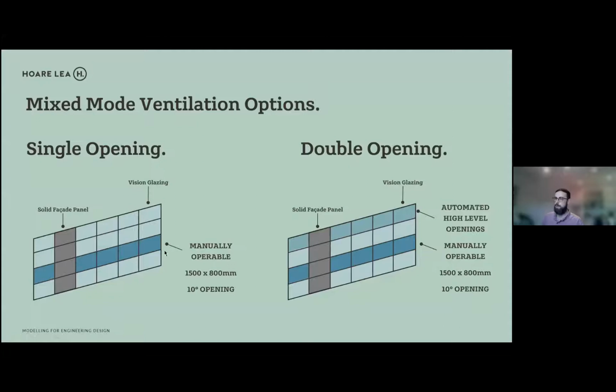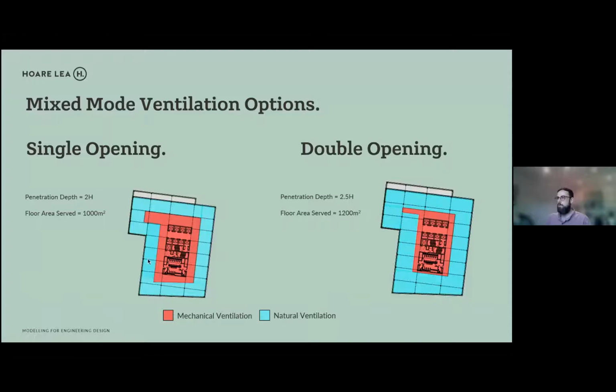Each of the windows is a set size, and a 10 degree restricted opening was provided. We look at a slice through the floor plate and how much of the HVAC we could control, which would then inform how much energy saving we could make.